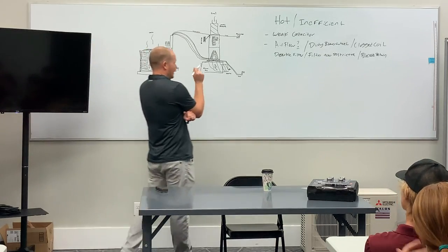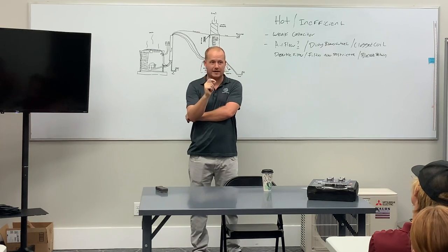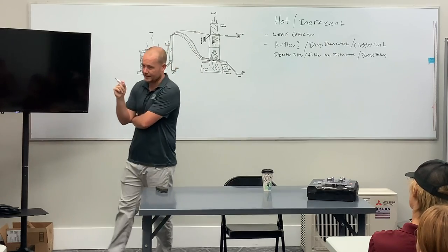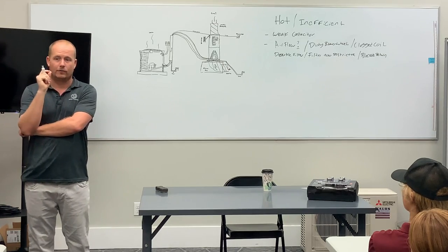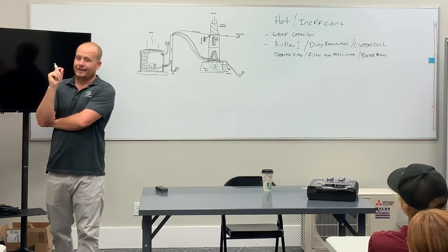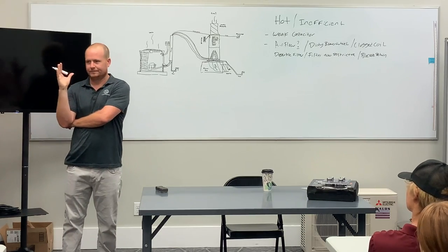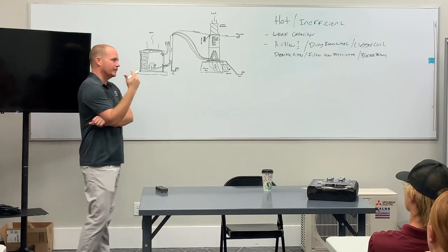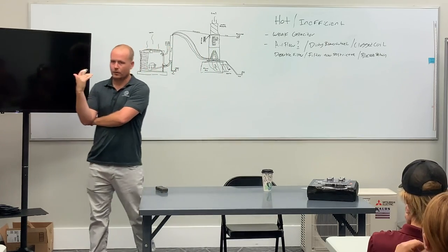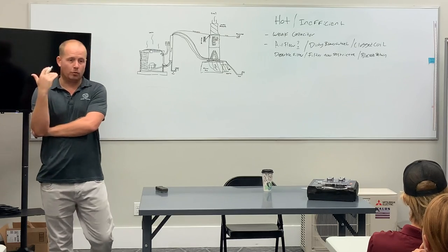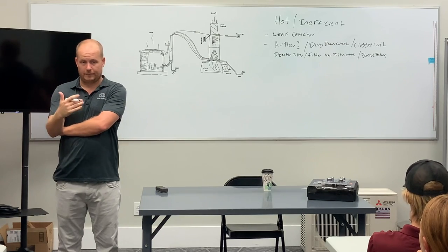So, does an airflow restriction on a regular PSC, does anybody know what PSC stands for? Permanent split capacitor, old school blower motor, not variable speed. Does an airflow problem, like a restricted evaporator coil, cause that motor to run hot or inefficient? Yes. And the answer is no. No with the caveat. Because of course it is an air-cooled motor, so I'm sure there would come a point at which it would cause it to overheat. But with a traditional blower motor, when you have poor airflow and you have high static pressure, does the motor draw higher current or lower current?